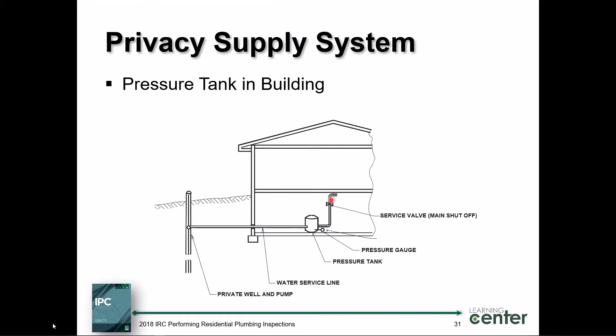The next one that you see here is what we call the water service pipe. This is where we connect up to a city public main water supply system. In a case like this, the water supply piping is probably right where it ties into the city main, and it goes all the way to this valve. Remember that demarcation I was telling you about earlier? Here it is. This is considered water service or water supply piping until it gets to the water service valve. When it comes out of the water service valve, it's called water distribution piping. Know the demarcation here, okay? That's exactly what we're looking at.